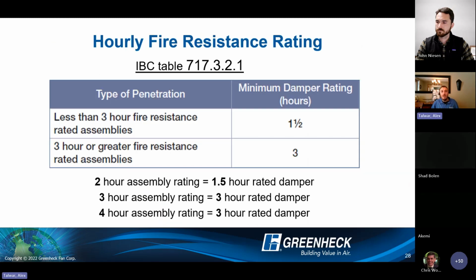All right, here's the important slide with the hourly fire resistance rating. Our 1.5 and 3 hour rated dampers: we can use the 1.5 hour rated damper in construction that's rated up to, but not including, a 3 hour fire resistance assembly rating. So if we have a wall that's rated 2.5 hours, we can use that 1.5 hour rated fire damper in that wall to maintain that rating.